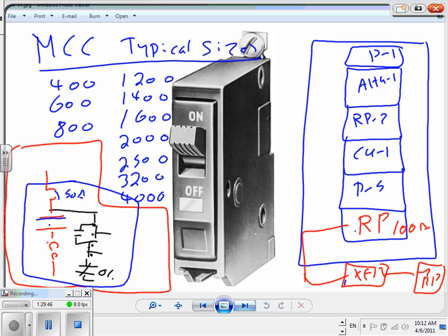MCC, I have never seen an MCC with a single pole circuit breaker, or even two pole circuit breaker. You would never. I mean, it doesn't pay to have an MCC with less than 3 pole circuit breakers. It just doesn't pay. If you have an MCC, most likely you have a 3-phase system, and you wouldn't use a single phase, 2-pole or 1-pole. 3-pole means 3 phase. Yeah, 3-pole means 3 phase. Yep, Mr. Bill.